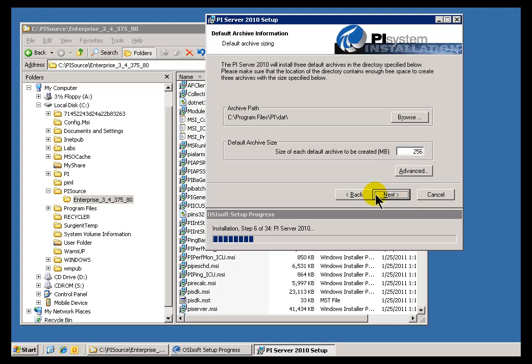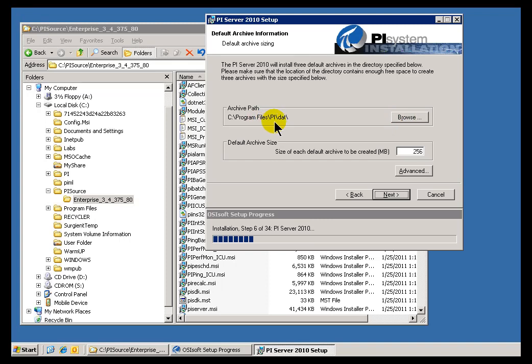Now next up, we get to specify where the Archive Path is, where the Archives are going to be stored. We haven't gotten into it, but suffice it to say that there are files, large files called Archives. There are three of them that are going to be created by default, and this is where we store the historical data. Typically they go into the PI directory under the DAT subdirectory, and that's a fine place to put them.